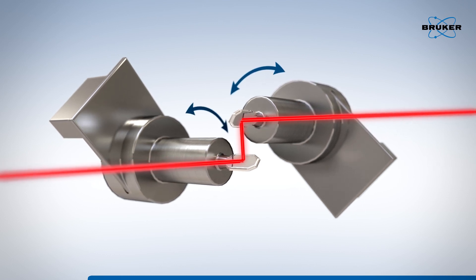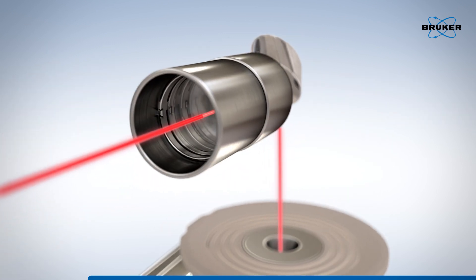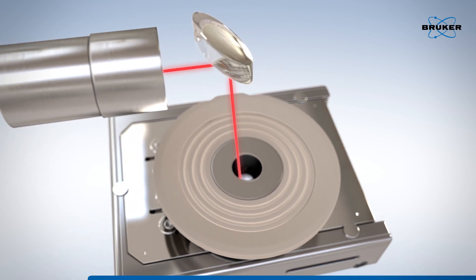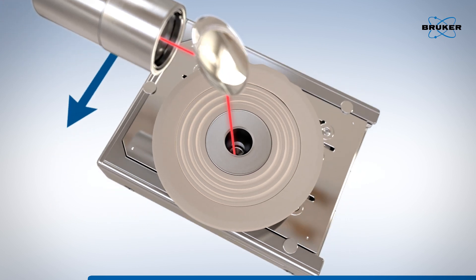Moving mirrors were added along with synchronized coordination between the target stage and laser positioning. The laser beam now travels inside the ion optics, offering improved ionization efficiency and longer time between each lens cleaning.